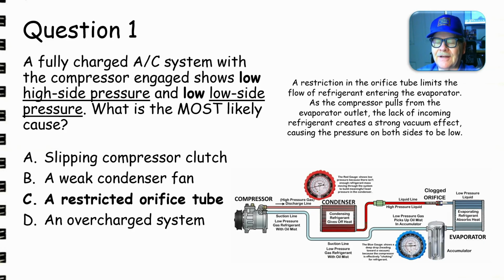There was this one guy who had done air conditioner work for years. He said, when I ran out of all other ideas on one with refrigerant issues, I always put an evaporator on it and it fixed it. But anyway, that's what we found on that one. So this is usually more likely to happen with an expansion valve problem than a clogged orifice, because the expansion valve can fail in such a way that it throttles the refrigerant all the time and doesn't work anymore, especially if that little alcohol diaphragm leaks and quits working or whatever.